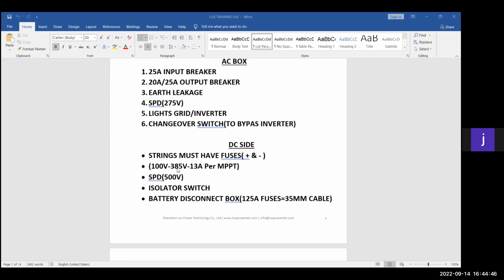You can go higher than that, but you lose slight efficiency on the MPPT side, but the MPPTs will still work and they won't get damaged if you go higher than that. I try to tell the clients, don't try to go higher than 400 to 410 volts on the VOC side of the MPPTs. Try to keep it between 120 and 400 is where I usually try to keep my panels. Then from there on, I recommend, as I said, the fuses must be in, then SPDs. A 500 volt SPD on your system will be sufficient to protect the MPPT if there's a very big spike coming through. Then an isolator switch to completely isolate your system.